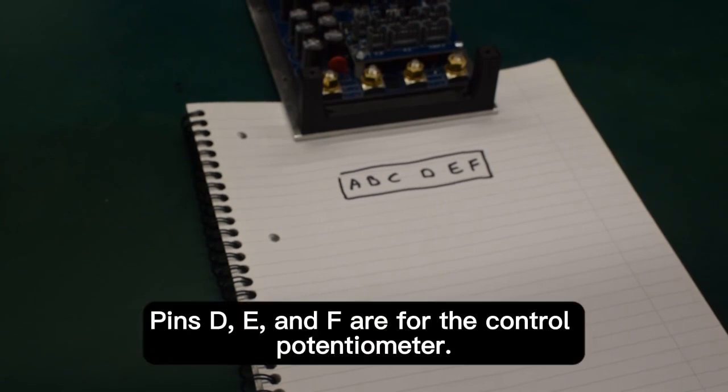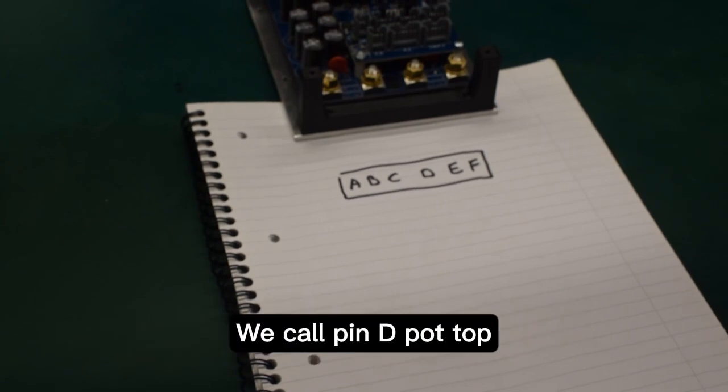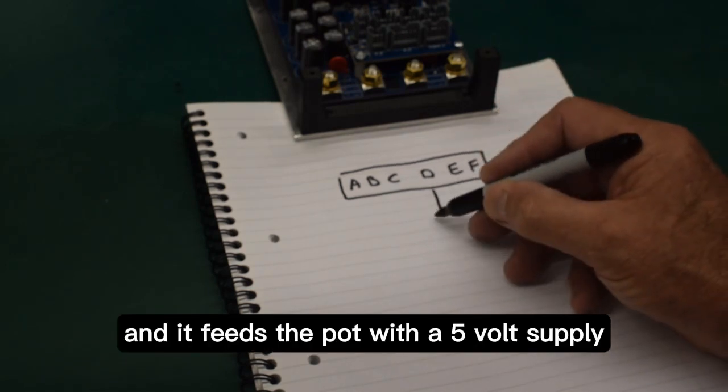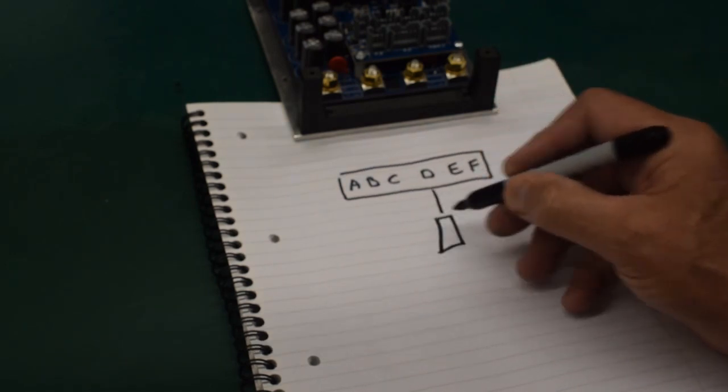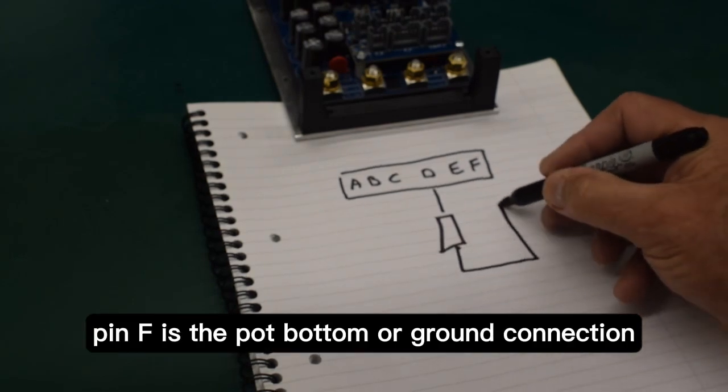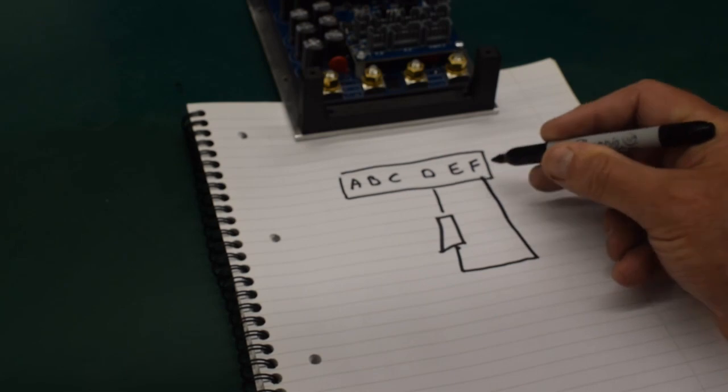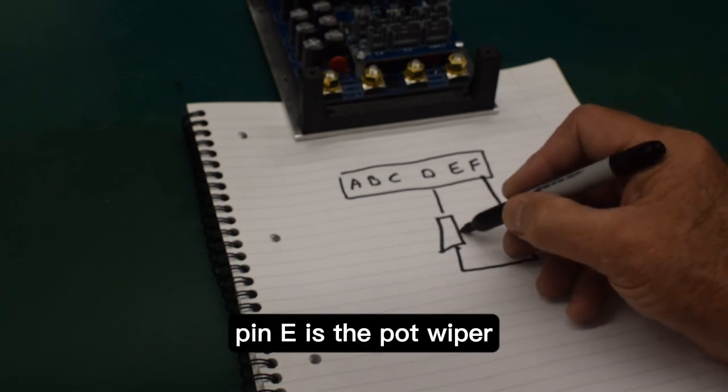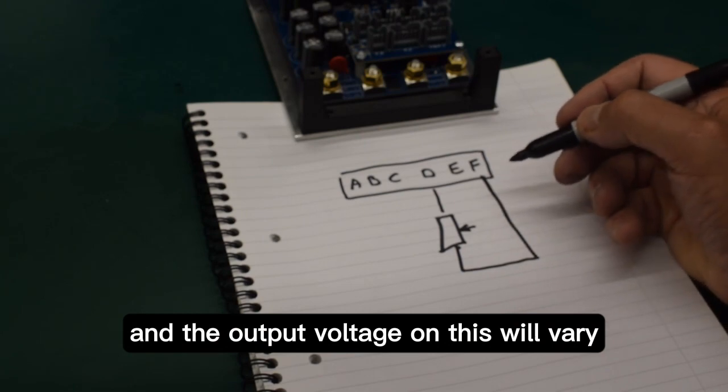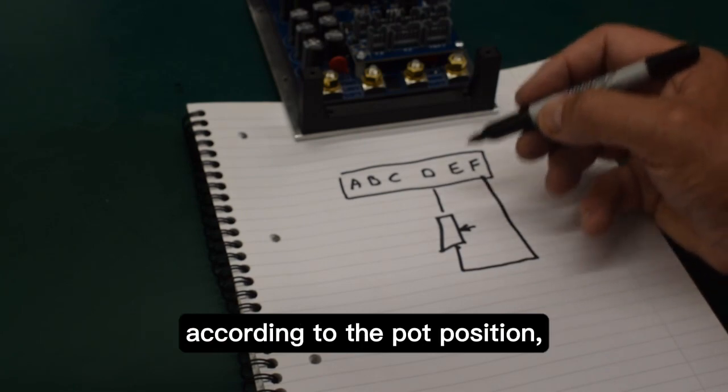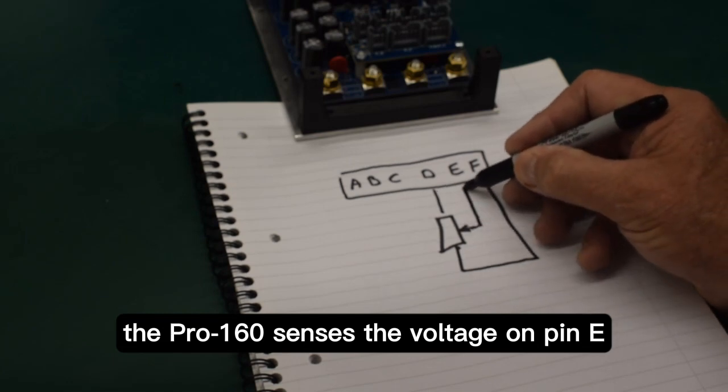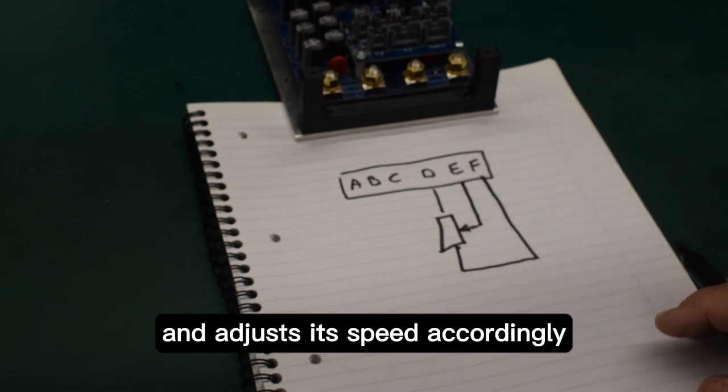Pins D, E and F are for the control potentiometer. We call pin D pot top and it feeds the pot with a 5V supply. Pin F is the pot bottom or ground connection. Pin E is the pot wiper and the output voltage on this will vary according to the pot position. The Pro 160 senses the voltage on pin E and adjusts its speed accordingly.